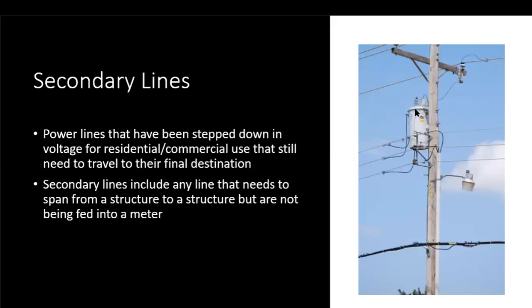If I'm coming off the transformer, or I'm feeding from the transformer down to homes or down the street, from structure to structure I'm going to need to have secondary lines, and these are those lines that you see in this picture right here. Now the secondary lines, as I said, go from structure to structure, and they're at secondary voltages.